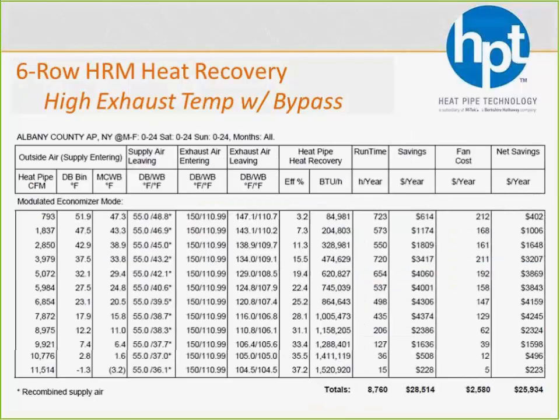And you can even go a step further, run a bin analysis, pick your location. In this case, it's Albany, New York. And again, we're assuming that we don't want to get any more than 55-degree air coming out of the heat pipe. So you can see on the supply air leaving, they're all capped at 55 degrees. So anytime the air is warmer than 55 degrees, we're not doing anything. It's full bypass. And anytime it's lower than 55 degrees, we're only passing enough air through the heat pipe to get 55 degrees.